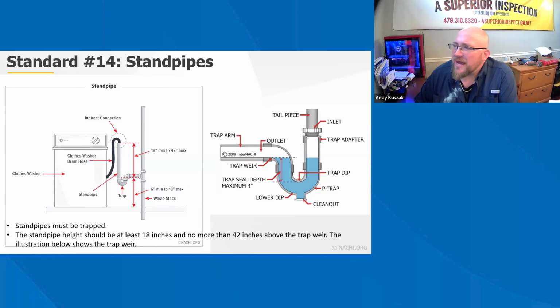To prevent overflow, the height limitation is necessary to provide some retention capacity and head pressure. The height limitation controls the velocity of the waste flow at the trap inlet. The limitation is necessary when a high rate of discharge enters the indirect waste pipe, such as that from a clothes washer. Excessive velocity will siphon the trap.